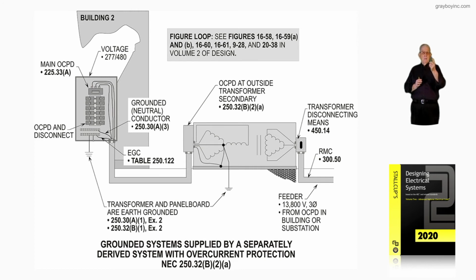But now the neutral would be calculated by 220.61. And you may have a 150 amp neutral, 200 amp neutral, or you may have a full 4-aught neutral in relation to the 4-aught conductor supplying that 225 amp main. So what this is pointing out again, we would use the larger of the neutral calculation, 220.61, or the equipment grounding conductor size per table 250.122 that we've looked at. But now notice this transformer and panel board are earth grounded, in my opinion, in accordance with 250.30(A)(1) exception 2 and 250.32(B)(1) exception 2.